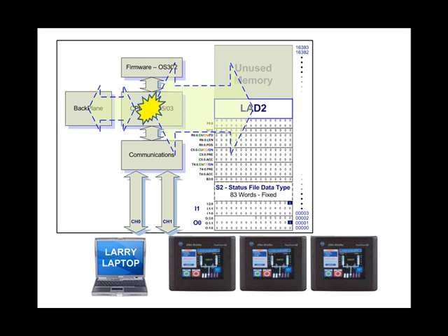This is followed by activating the output modules one at a time sequentially over the backplane and transferring the data from the controller's memory to each module associated with that word of memory to control the output devices. This is the primary cycle that people identify with the PLC. Collect inputs, execute the logic, storing the results, and then sending out the results to the output modules.